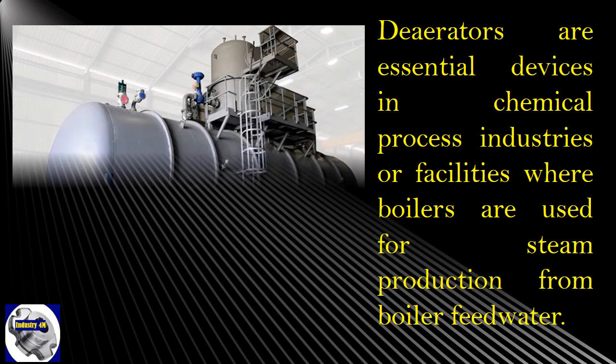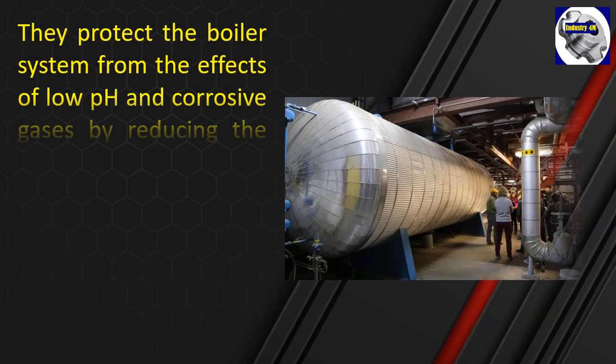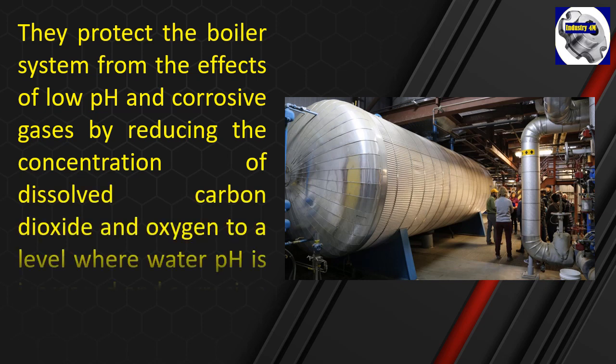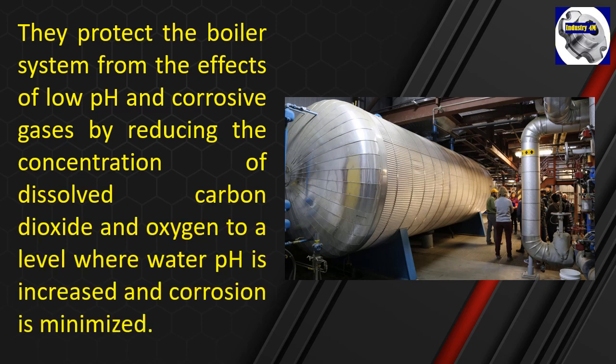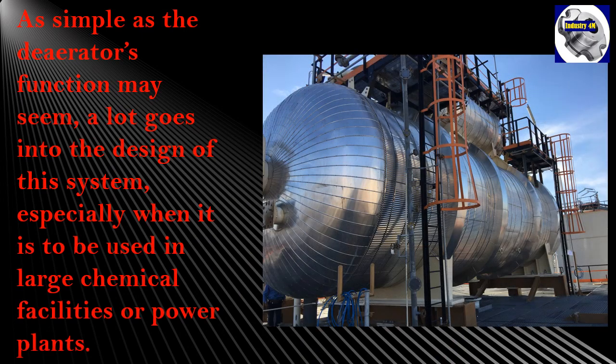Deaerators are essential devices in chemical process industries or facilities where boilers are used for steam production from boiler feed water. They protect the boiler system from the effects of low pH and corrosive gases by reducing the concentration of dissolved carbon dioxide and oxygen to a level where water pH is increased and corrosion is minimized. As simple as the deaerator's function may seem, a lot goes into the design of this system, especially when it is to be used in large chemical facilities or power plants.